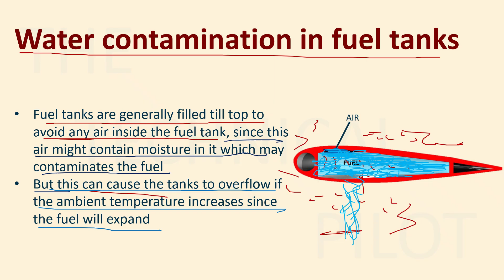But what happens if you fill the tank completely? If the ambient temperature changes, for example, it was cold outside when the fuel tanks were filled, and in the morning there was sun, so there was heat outside. Now this heat will heat up the fuel inside the tanks, right? And when the fuel gets heated up, it will expand. Anything when you heat it up will expand. Since there is no room for the fuel to expand because we filled the tank completely, this fuel will start to leak, and this is embarrassing, right? This can cause the tanks to overflow if the ambient temperature increases, since the fuel will expand. So this is an issue that you should be aware of.